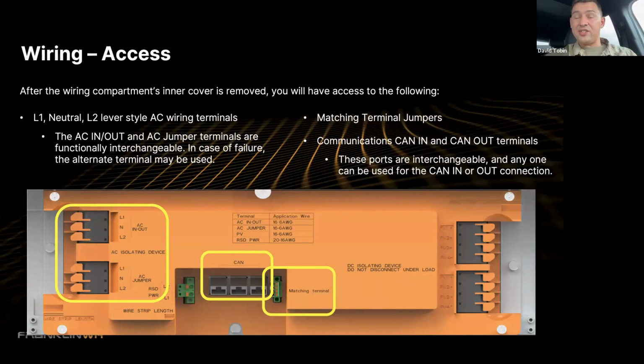We use a CAN 2.0 communication method. So you have a CAN wire between our aGate and the aPower S. And then the matching terminal, this is what closes out the CAN communication. So if you have multiple batteries, you just remove that matching terminal on all the batteries except for the last one to close out the loop.